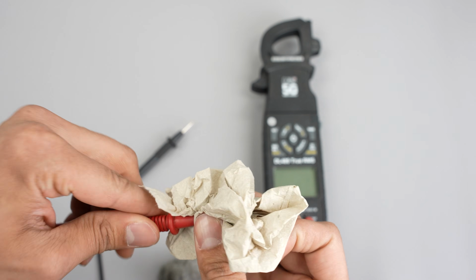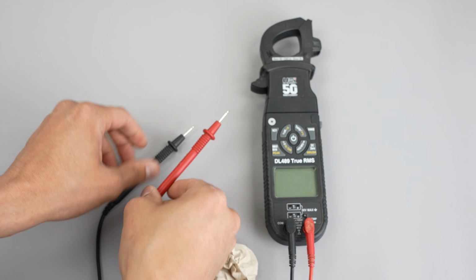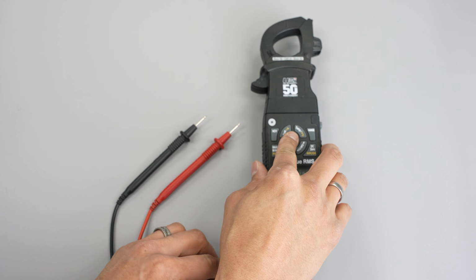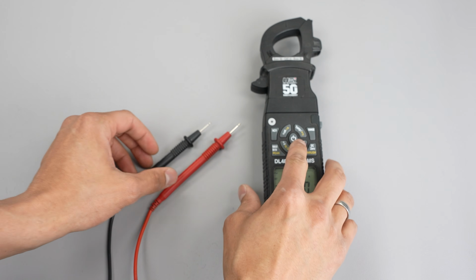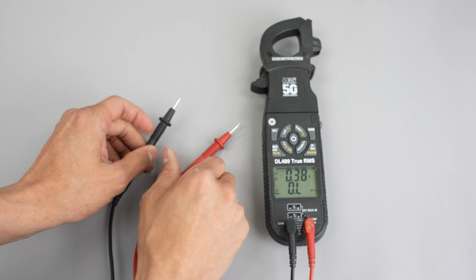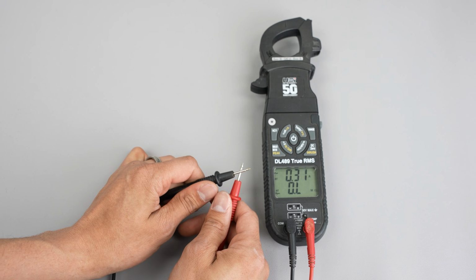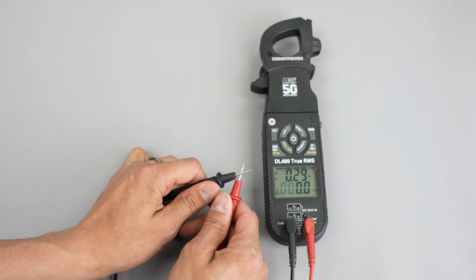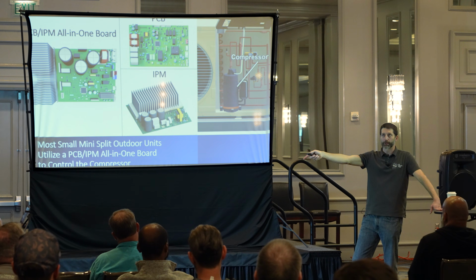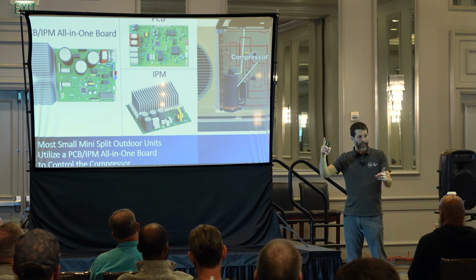If I see that my probes are reading more than like 0.1 ohms of electrical resistance, those probes are going in the trash. I'm going to put new probes on, because that's going to mess up your electrical resistance readings for everything that you're measuring, everything. It's the same thing as calibrating your temperature reading instruments. Those probes can go bad over time, and they will go bad.